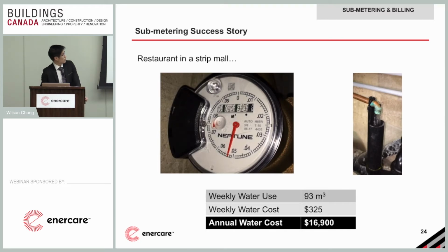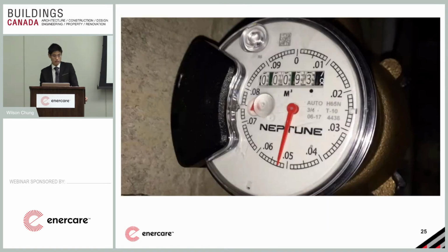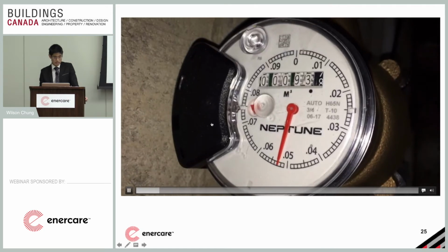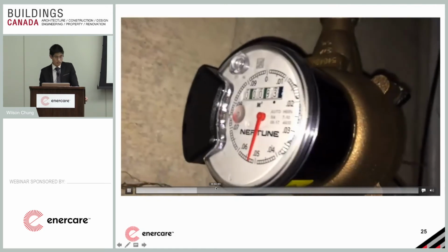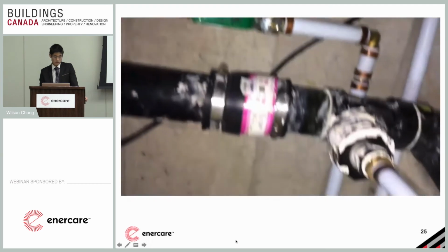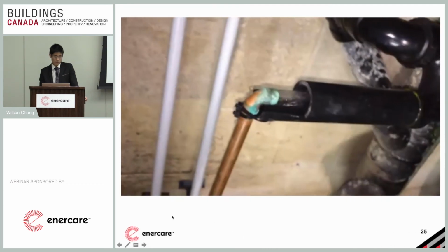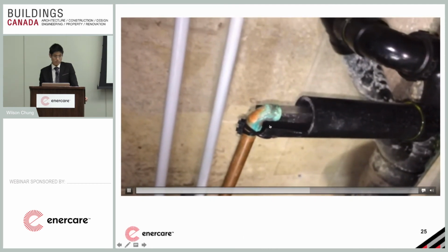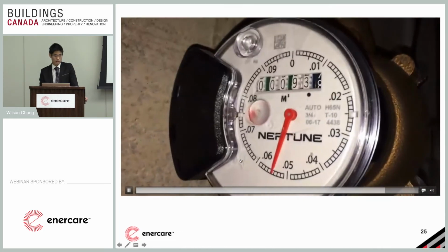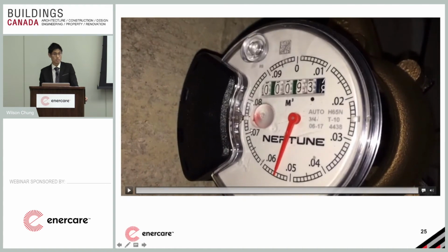We have an interesting physical example from a commercial retail site—a restaurant in a strip mall built with single-pass condensing units for the walk-in freezer. If we look at this, you can see the meter continues to spin. To the left, that's your water going straight to drain from the condensing unit. Look at the speed at which this meter is spinning—that's just continuous consumption going down the drain.